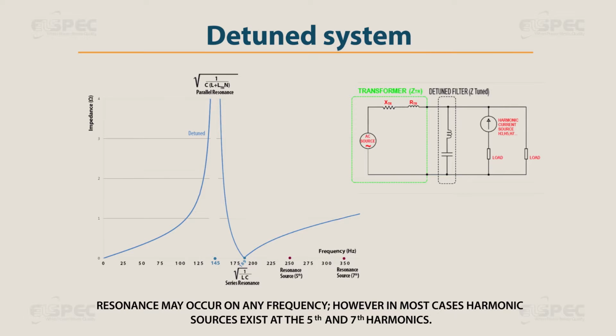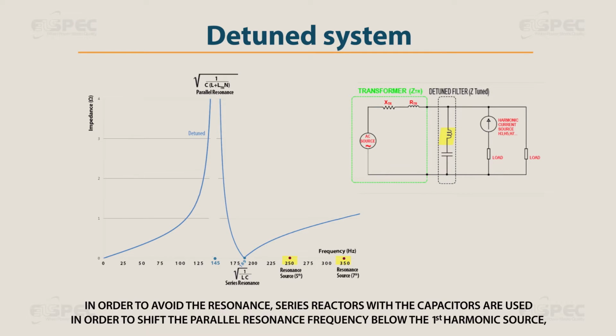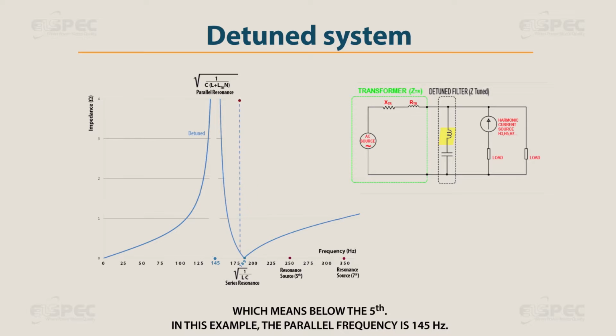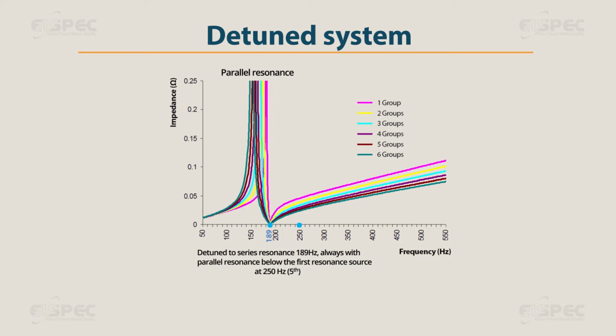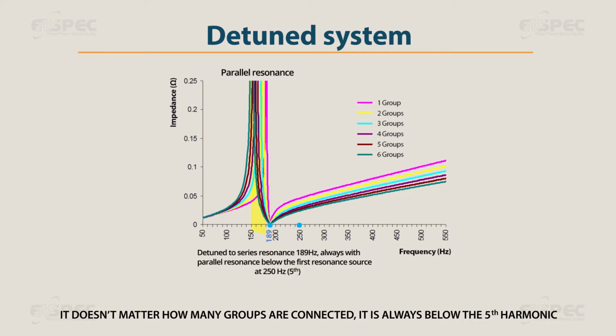Resonance may occur on any frequency. However, in most cases, harmonic sources exist in the 5th and 7th harmonics. In order to avoid the resonance, series reactors with the capacitors are used in order to shift the resonance frequency below the 1st harmonic source, which means below the 5th. In this example, the frequency is 145 Hz. It doesn't matter how many groups are connected, it is always below the 5th harmonic.